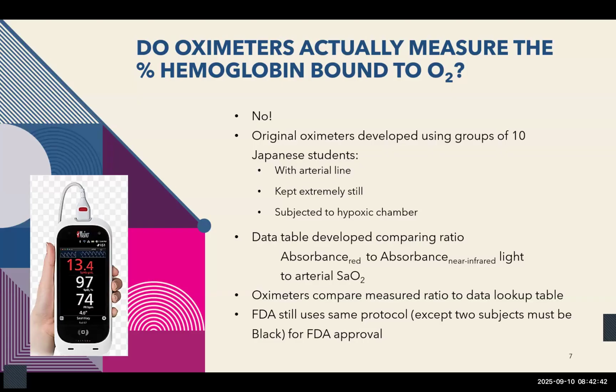So you look at the ratio of the density that comes out at the two different red wavelengths, and you record that. And then in a machine like this, instead of measuring all these cool things, it has a little data table built into its memory chip. And it says, okay, if my ratio is this, according to the table that we came up with in our lab, your O2 saturation is that. So it's really just measuring a table rather than anything else.